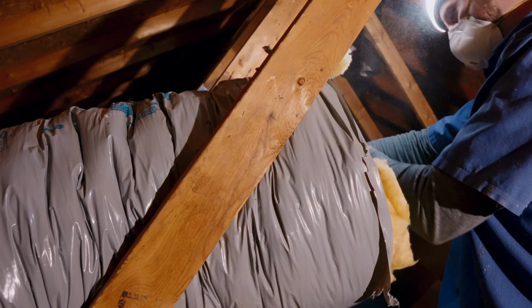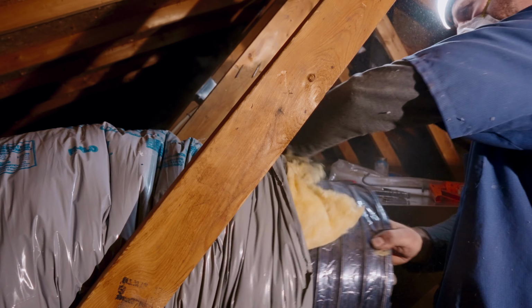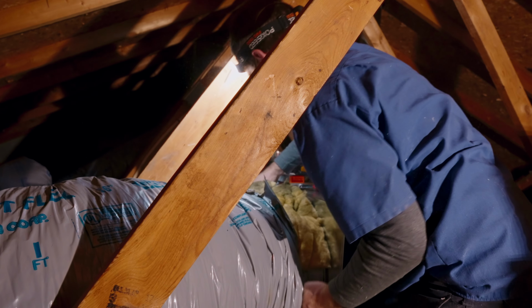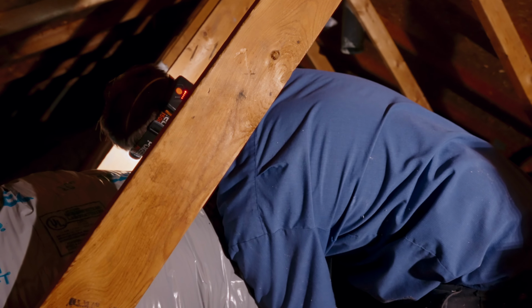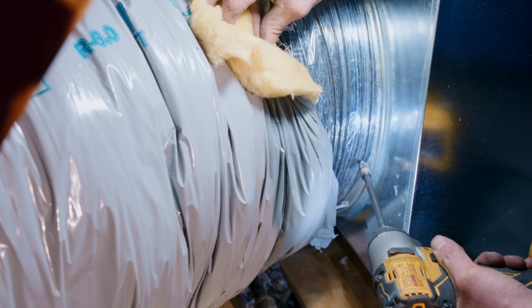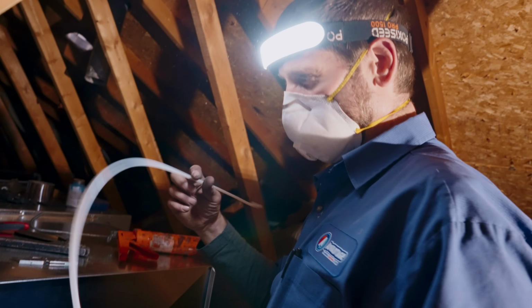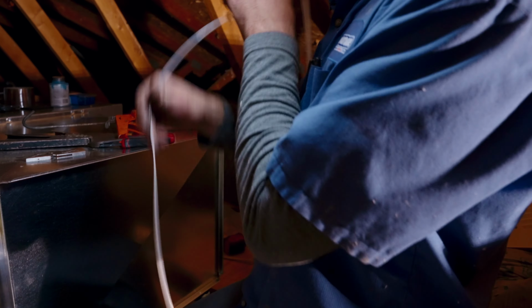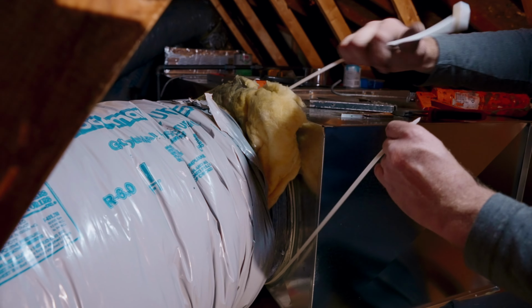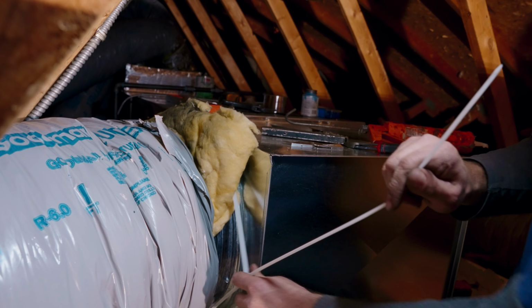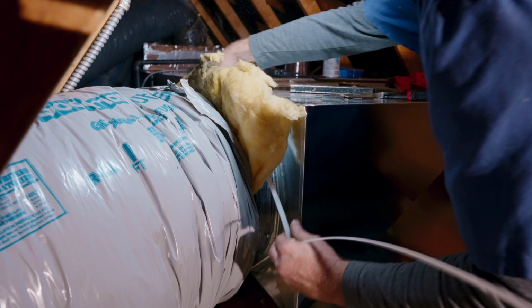So I just push the insulation back. Feed that over the flex collar. Use screws. They're called Panduit straps. They're giant zip ties, is what they are. Probably have to double it up. Usually do on this bigger pipe. And I'll put one on the liner duct and then on the actual insulation outside. Making sure I push all the insulation up to the plenum. That way there's no bare metal that's not insulated from the inside or the out.